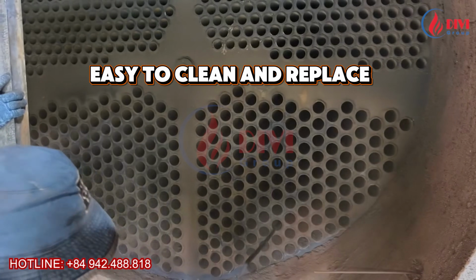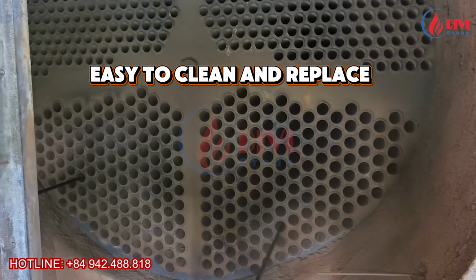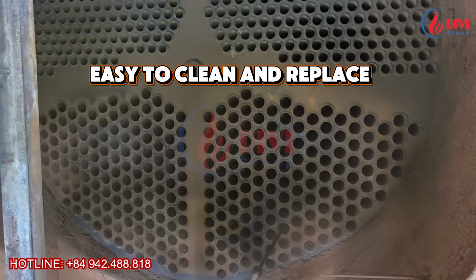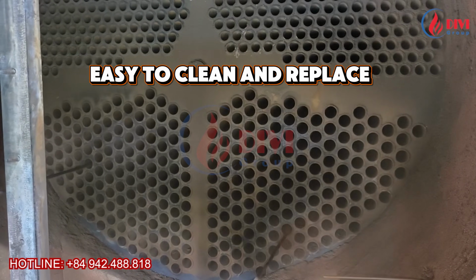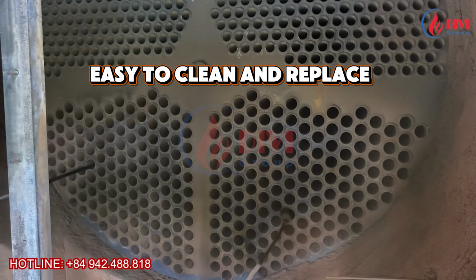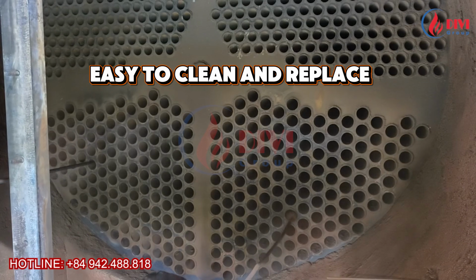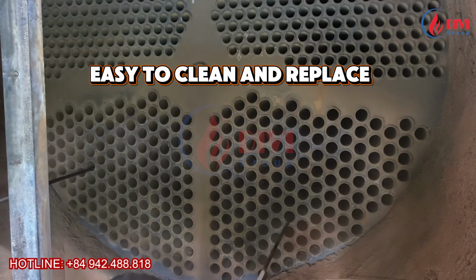By opening the inspection doors, each fire tube can be cleaned individually. If a fire tube becomes damaged, replacing an individual tube is generally easier than in many water tube boiler designs. This is a very practical advantage when it comes to maintenance and repair.